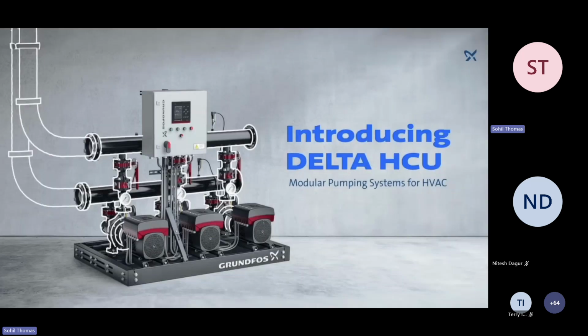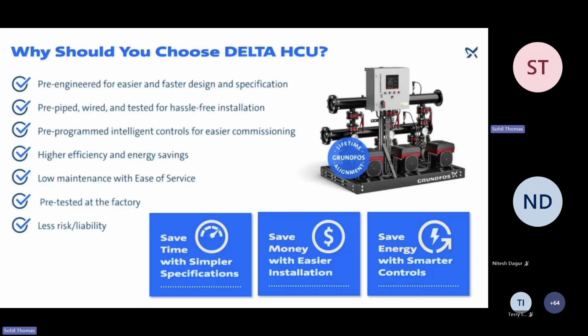That's why we have the same applications available for HVAC systems too, which is called the Delta HCU, Delta Heating Cooling Unit, where a similar package system like what we saw for Hydro MPC for plumbing, we use for heating applications. Again, this comes as a complete package system, complete with discharge and suction manifolds, integrated drives, controllers and isolation valves, and it comes from Grundfos pre-wired, pre-factory tested, and it's smooth for installation for the contractors too. So why do we choose this? It's basically because of the 3 boxes that you see below. It saves time, saves money with easier installation, and it saves a lot of energy because the controller is doing the job for you, maintaining the highest efficiency at all levels.